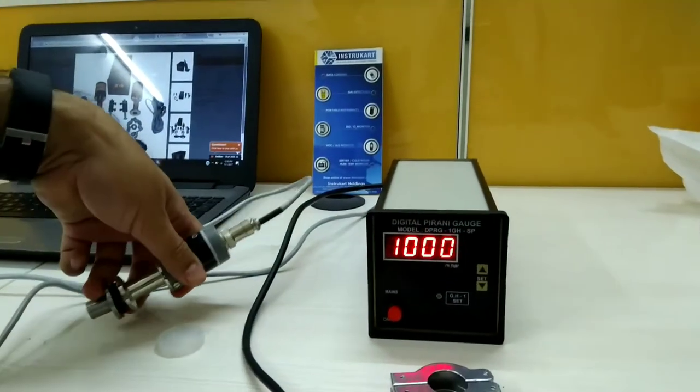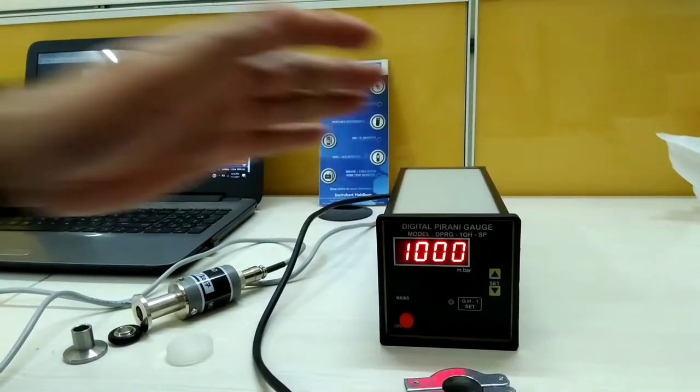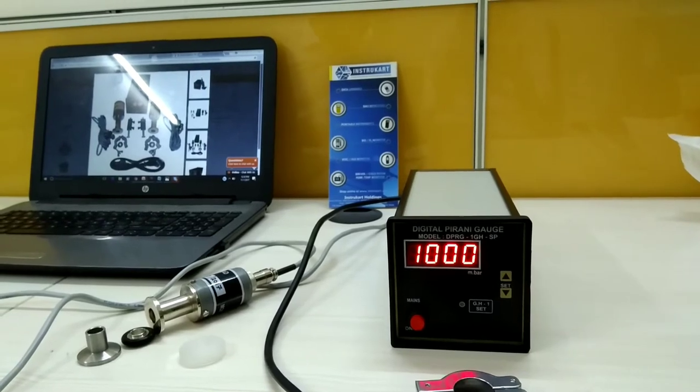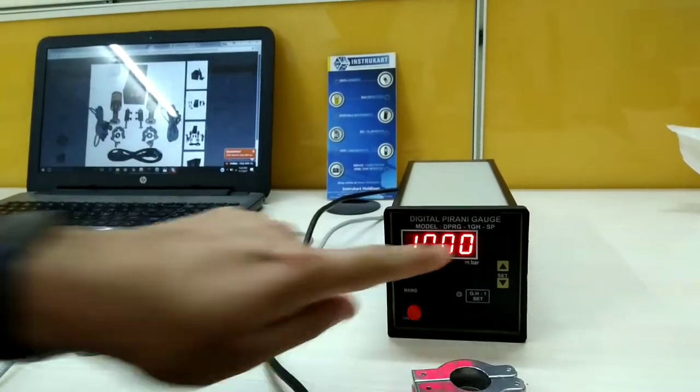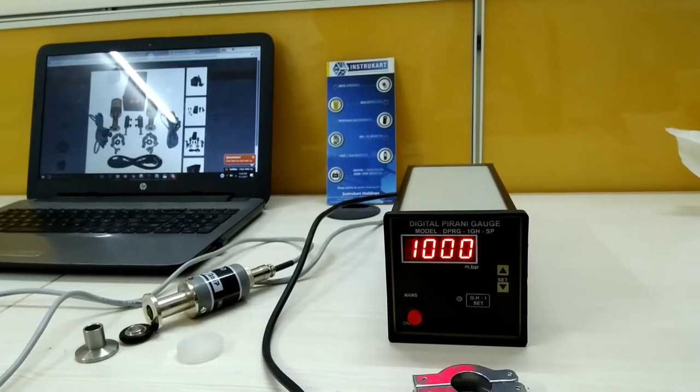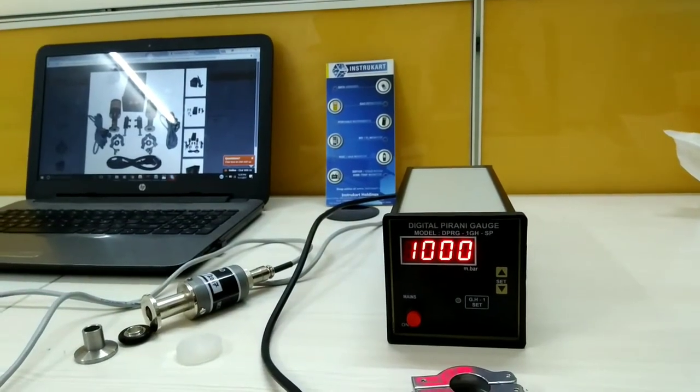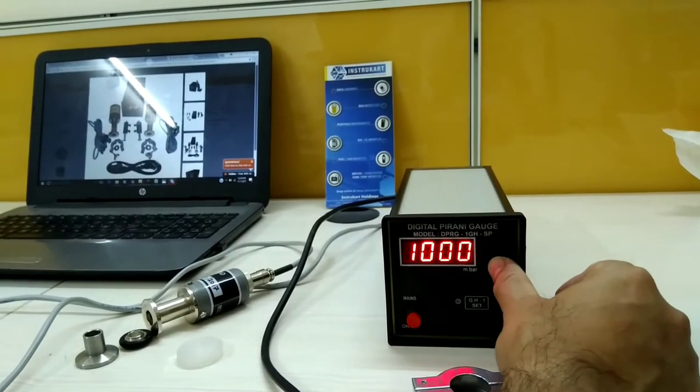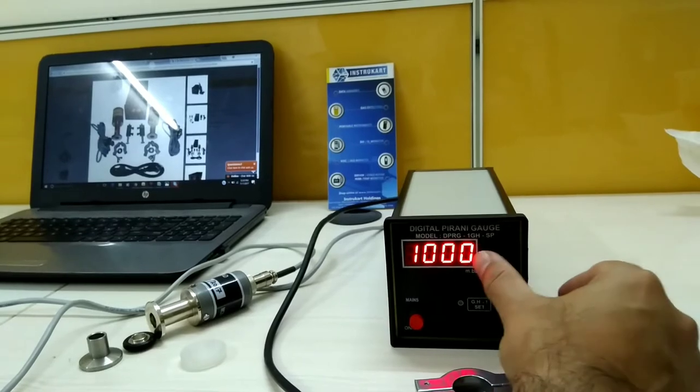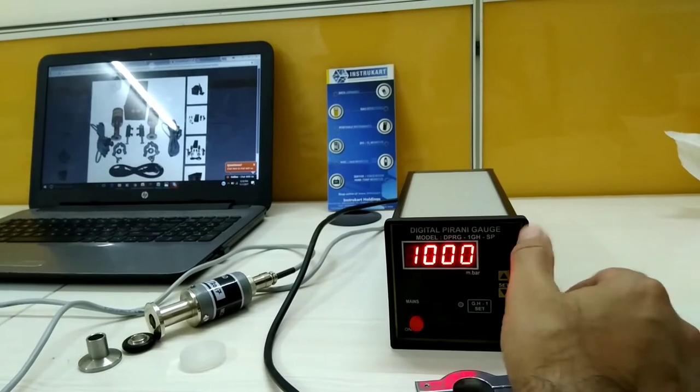The Pirani Gauge Head and Pirani Sensor along with the Pirani Gauge measures from 1000 millibar right up till 0.001 millibar, that is 10 to the power of minus 3 millibars. A traditional Pirani Gauge which you can buy separately would not have a setpoint provision. A setpoint provision is a relay output at any desired vacuum value throughout its range of 1000 millibar to 10 to the power of minus 3 millibar.